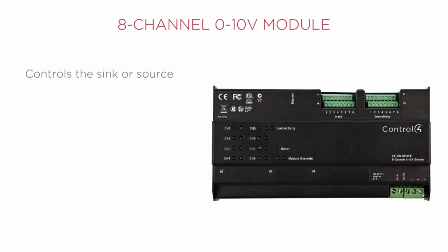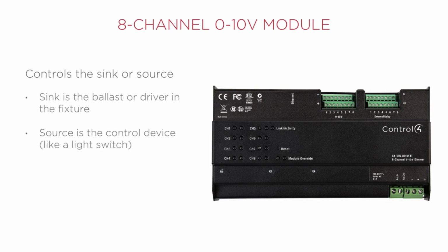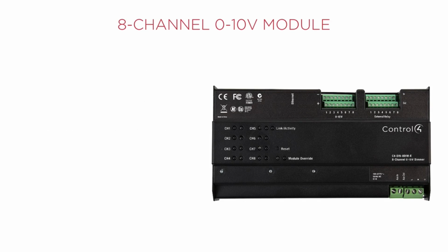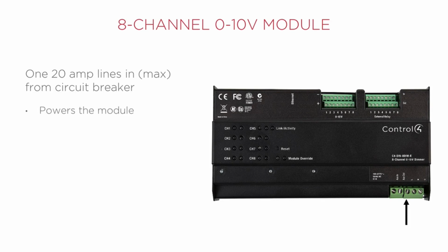Knowing the naming convention is important in order to determine how many ballast or fixtures can be connected and controlled. The dimmer module can control the sink or the source. The sink is generally the ballast or the driver in the fixture. The source is the control device or the light switch. The 0 to 10 volt dimmer module takes one 20 amp line in from the circuit breaker, which is used to power the module. 8 low voltage outs are used to control each load.